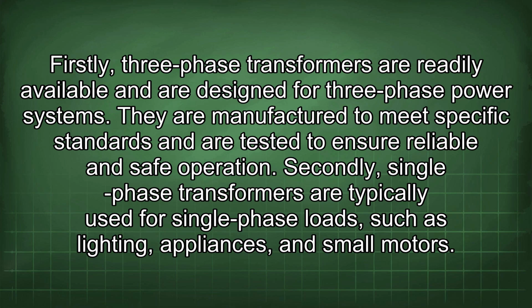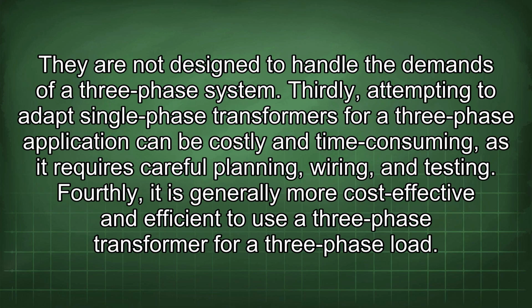Firstly, three-phase transformers are readily available and are designed for three-phase power systems. They are manufactured to meet specific standards and are tested to ensure reliable and safe operation. Secondly, single-phase transformers are typically used for single-phase loads such as lighting, appliances, and small motors. They are not designed to handle the demands of a three-phase system. Thirdly, attempting to adapt single-phase transformers for a three-phase application can be costly and time-consuming, as it requires careful planning, wiring, and testing. Fourthly, it is generally more cost-effective and efficient to use a three-phase transformer for a three-phase load.